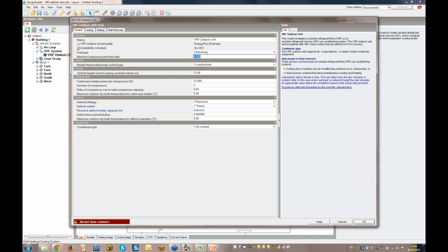The minimum heat pump part load ratio setting is the operating point below which the unit will cycle on and off. Above this point, the inverter will vary the compressor speed at each time step to meet the load, improving the efficiency of VRF compared to traditional non-inverter systems. There are a range of control types that can be used, and these are explained in DesignBuilder's fully integrated searchable help file, along with all the other VRF inputs. At the bottom of the General tab, we can select the condenser type, which can be air, water, or evaporatively cooled.